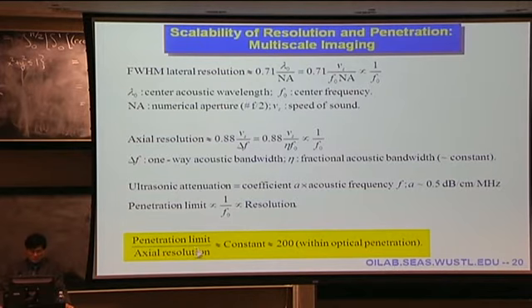Let's just focus on the bottom line. If you look at the lateral resolution and axial resolution, they both are inversely proportional to the ultrasound frequency used. But the penetration capabilities are also inversely proportional. If you take the ratio, right, between the penetration limit and axial resolution, you get roughly a constant. Very likely that constant is about 200. So that means you have 200 pixels in the depth direction to work with. And whenever you get more than 100 pixels, you get a decent image to work with.